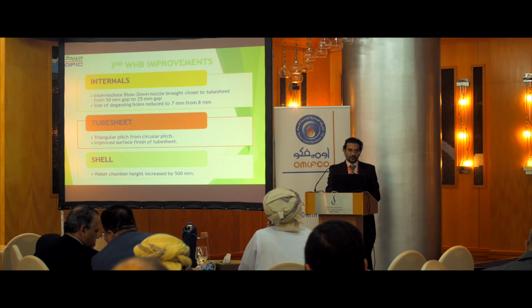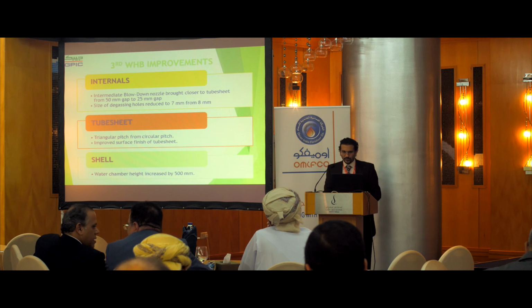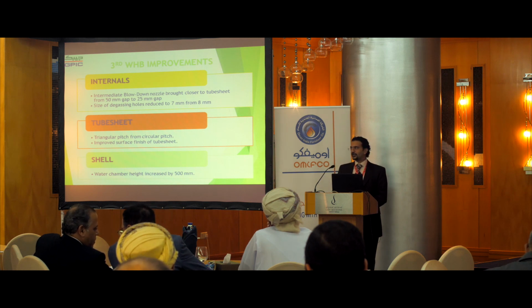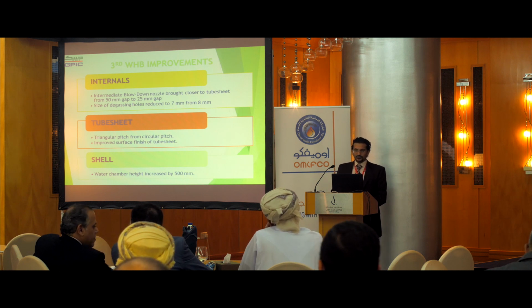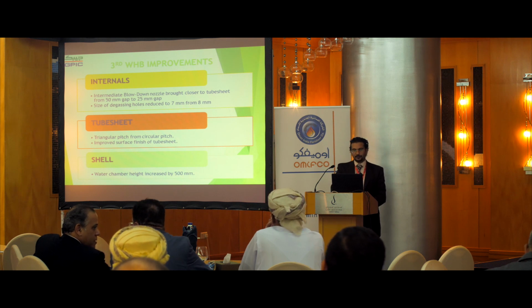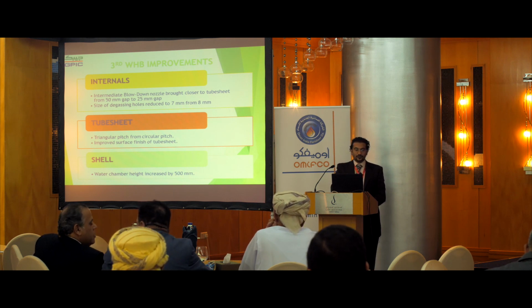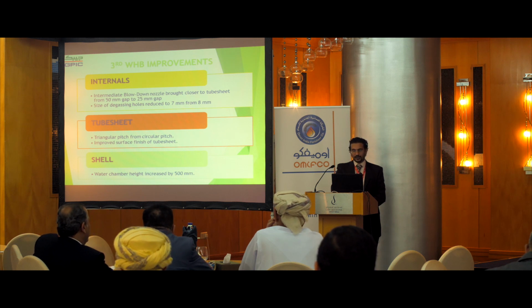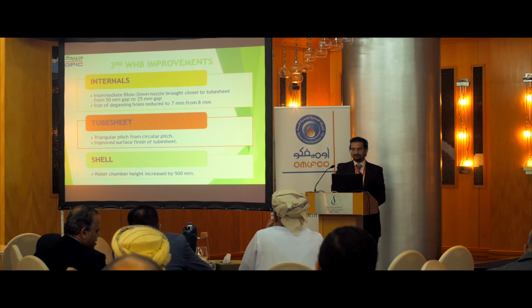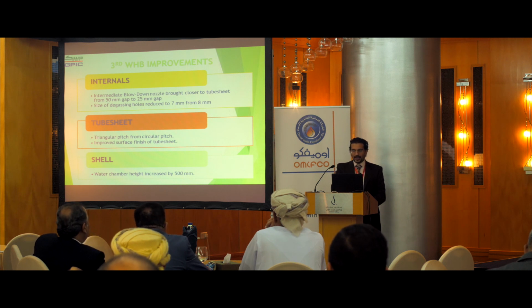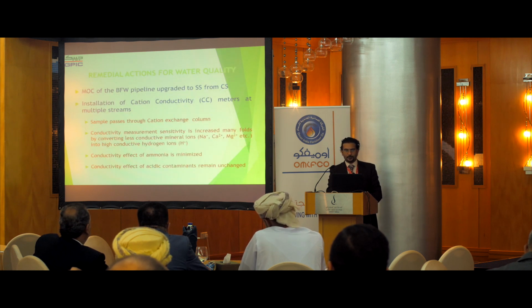For the third waste heat boiler, the improvements: the IBD, intermediate blowdown nozzle, was brought closer to the tube sheet, so there shouldn't be any collection of deposits in between. Size of the degassing holes was reduced to 7 mm from 8 mm. For the tube sheet, we chose to have the triangular pitch. It was better for our continuous blowdown, and improved the surface finish of the tube sheet, which means I think they did it in a smoother way. And for the shell, the water chamber height was increased by 500 millimeters.